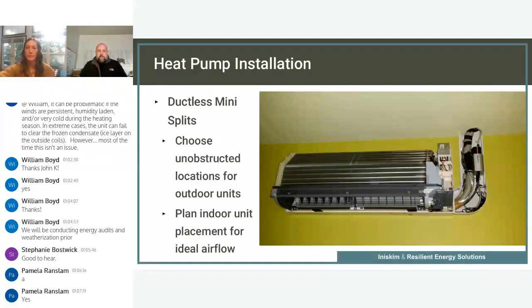But typically, this involves about a 4-inch or so hole being cut into the wall and a mounting bracket to hang the unit on, and running all of the refrigerant lines and the wiring. There's a power wire, signal wire, and condensate line out the back of the unit. So there's no conduit exposed in the house for a really clean finish. And again, we want to make sure that we're trying to put it in a situation where that condensate line can drain to the exterior. We don't want the unit filling up with water and not being able to push that condensate out.